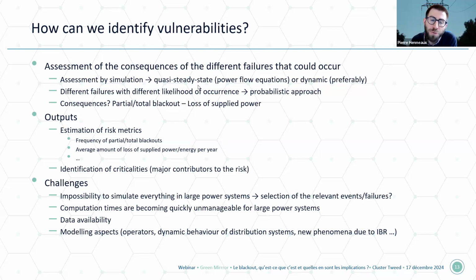We can simulate that using quasi-steady state simulation, so the power flow equation. So we'll assess after each event what will happen to the power flow in the grid, or we can simulate the dynamic behavior of the grid. You see that in blackouts, we usually have a fast cascade occurring at some time, so it's usually preferable to have a dynamic simulation to assess what will happen following outages.